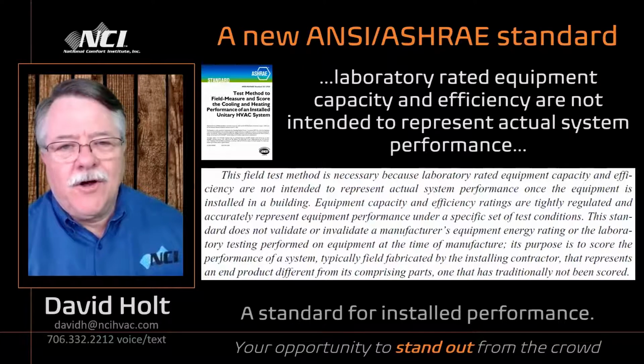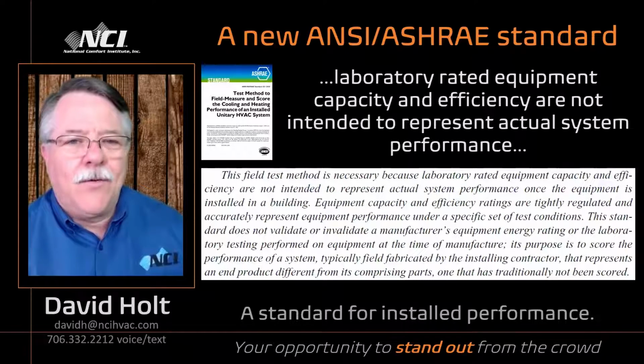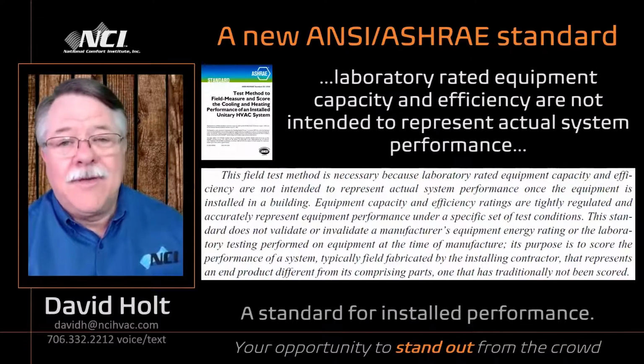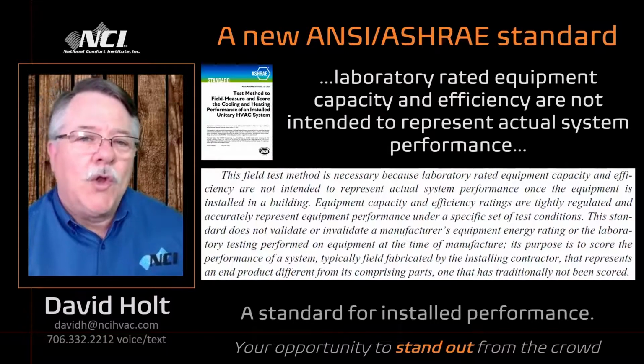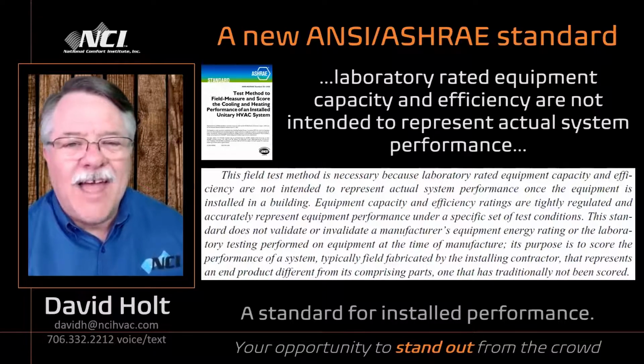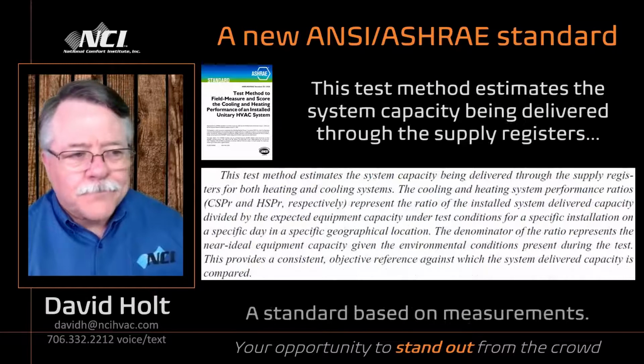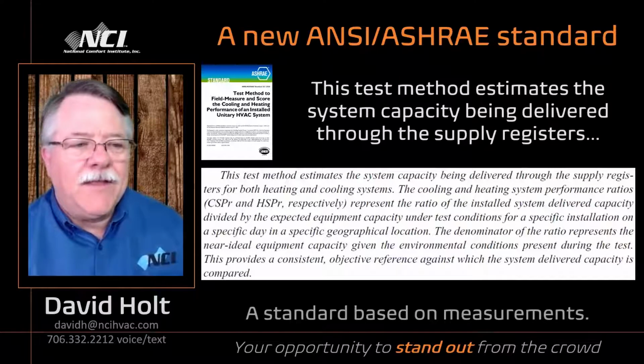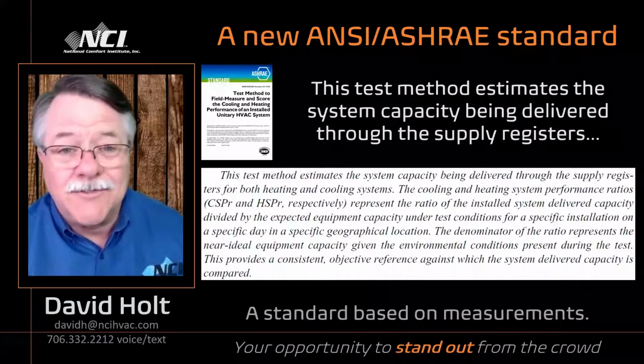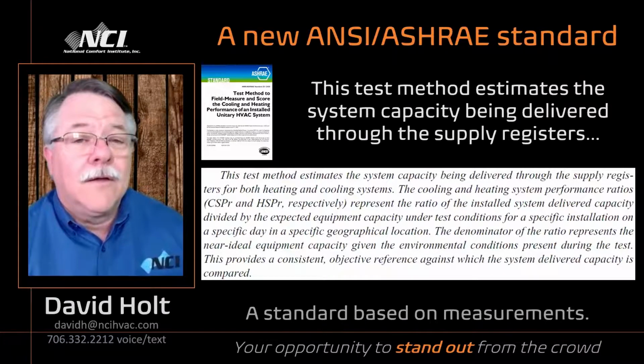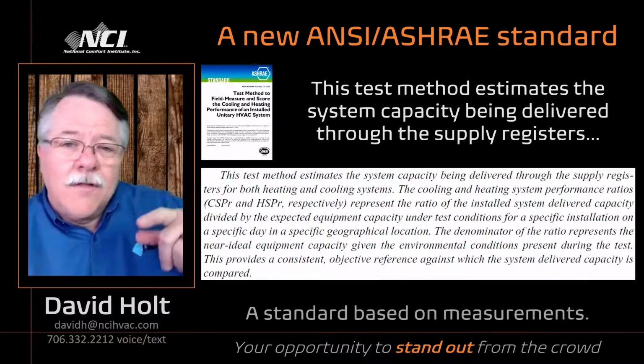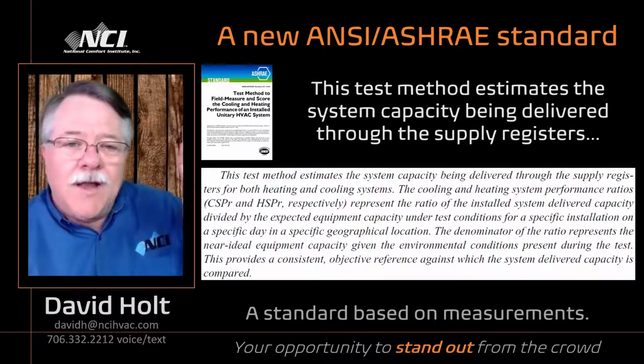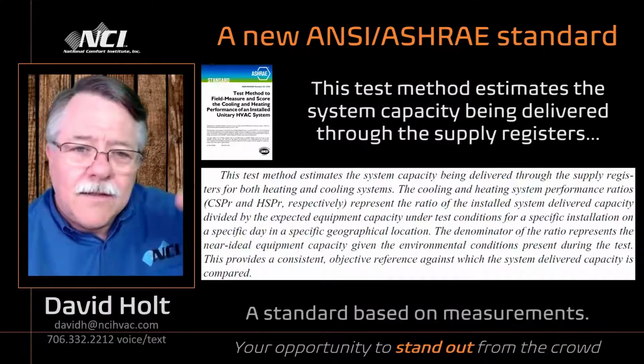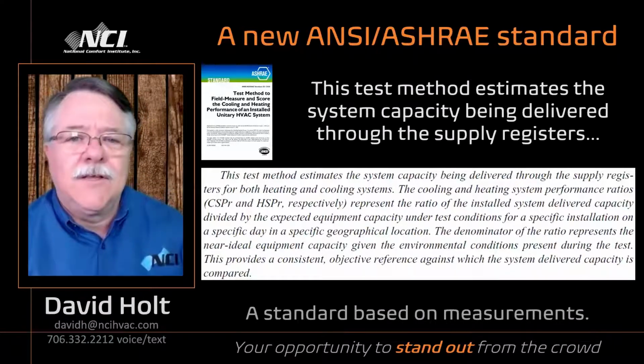This approach helps you stand out from the crowd in a big way, because this is all about a standard for installed performance, not designed performance. This test method estimates the system capacity being delivered through the supply registers—the product we're measuring is what's coming out of the supplies to keep the structure comfortable and the folks that live in it.